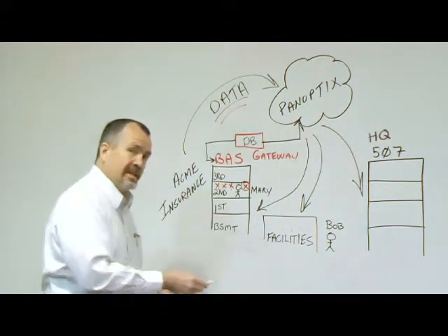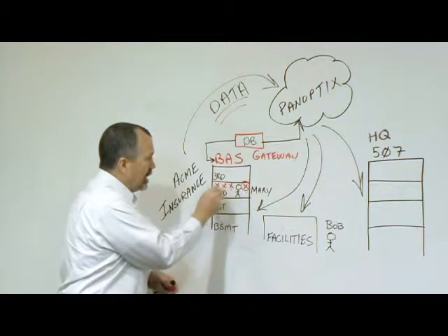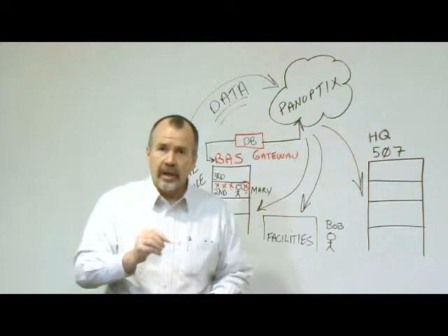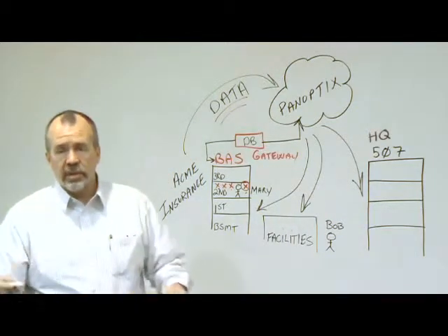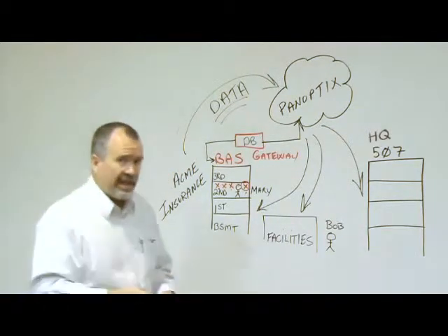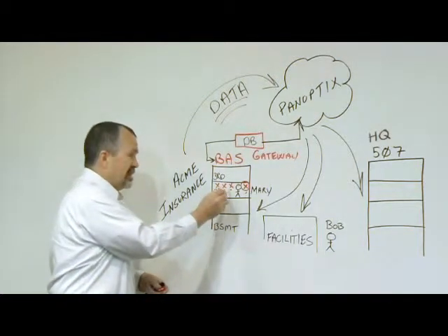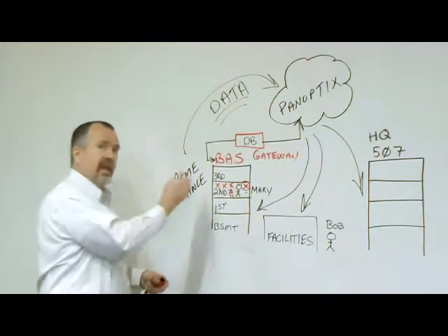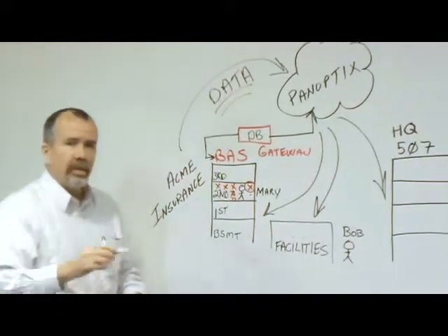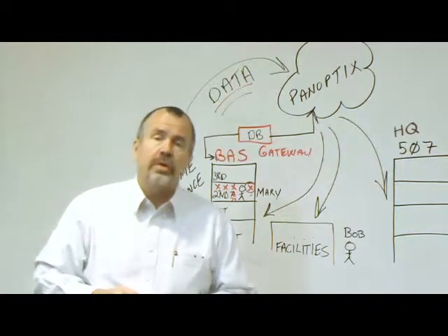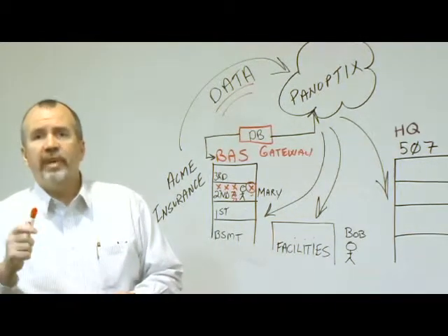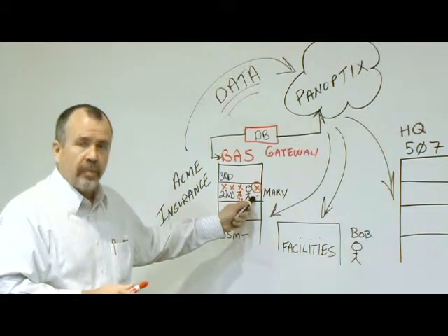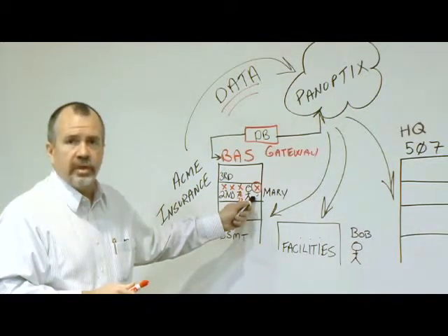If that's the case, we're going to be able to take a look at each box and say, does the problem that exists in Mary's area, in other words, the temperature is 78 but the set point is 72, does that exist someplace else? Is it 76 and 72 over here, and 78 and 72, and 80 and 72 in different areas? Then wouldn't you be able to logically assume that the problem doesn't exist with Mary's variable air volume box, that the problem exists with the air handler that serves that floor?